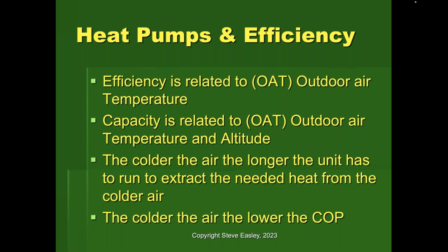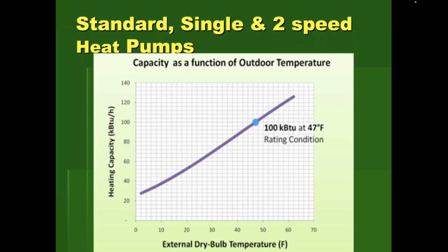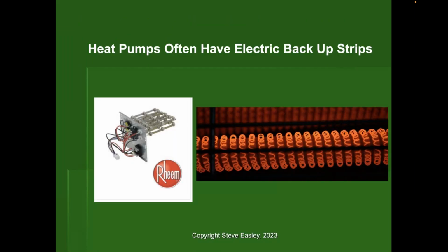And so that's why it's important that we have our ductwork insulated, our ductwork sealed, our building envelopes well insulated, our building envelope fairly airtight before we would want to retrofit a heat pump. Now, it's also important to recognize that a lot of the systems require that you have backup strip heating in the older traditional heat pumps. That's because of 2 reasons. One, you just needed it to be able to heat your house because the older technology heat pumps just didn't have that good of a capacity to extract that heat out of the air. And so once you got down into the 20s, or in some cases even higher than that, it didn't cost you any more to run these electric resistance strip heats than it did to run your heat pump because it just had to work so hard to extract that heat out of the air.